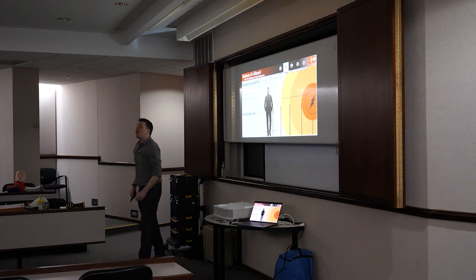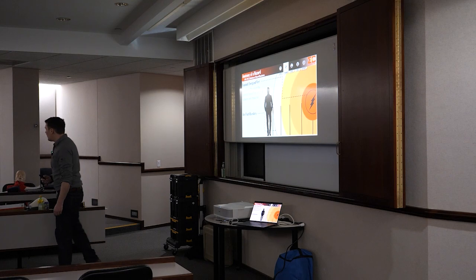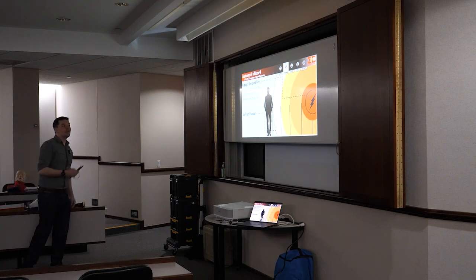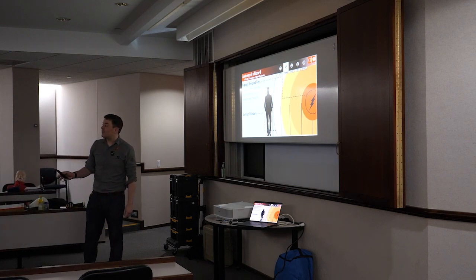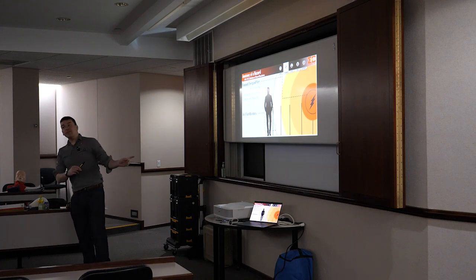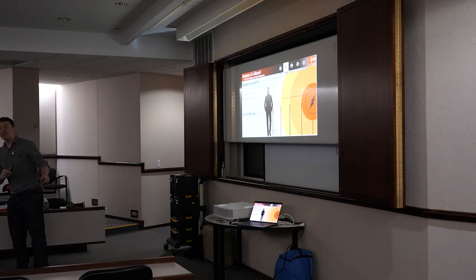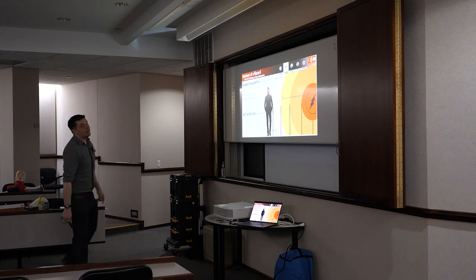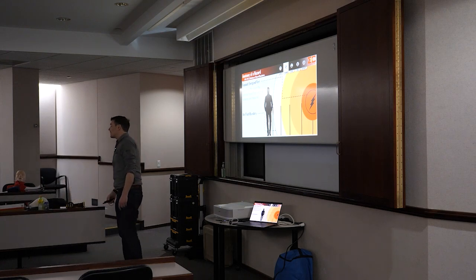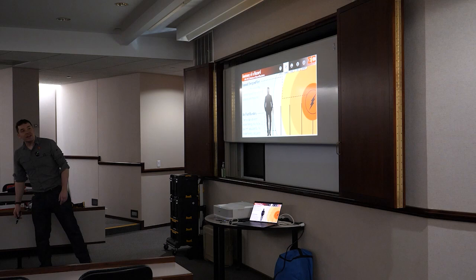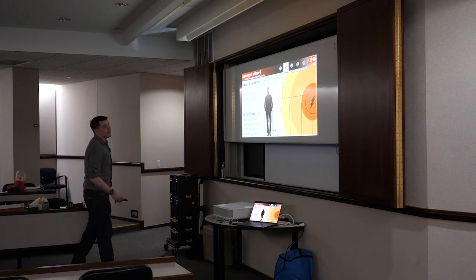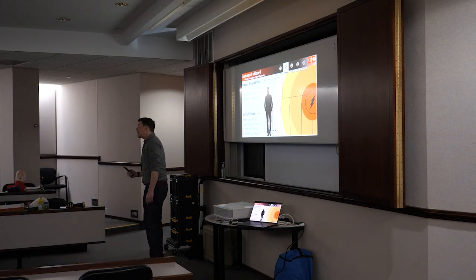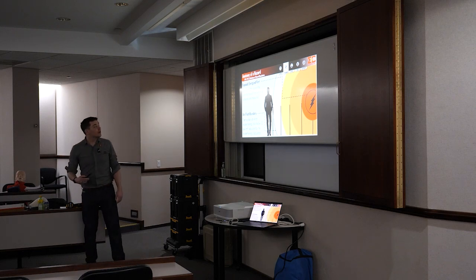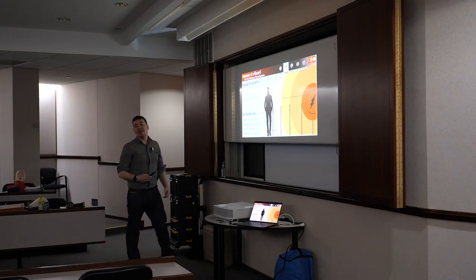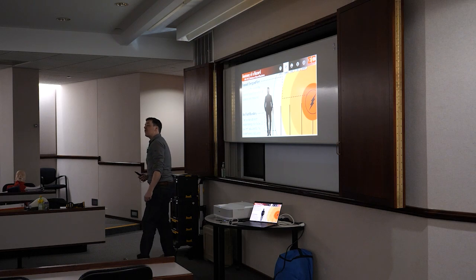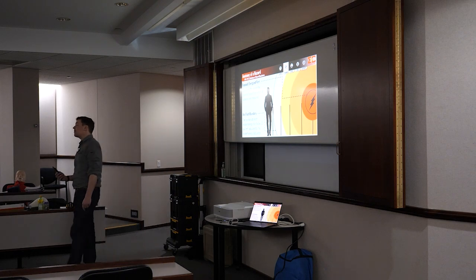Understanding what the different areas and what the different boundaries are when we deal with the equipment. For those of you who are looking to take your NETA exam, you should be very familiar with these because NETA 2 and NETA 3 love to throw questions about the shock protection and arc flash protection boundaries. At the center of it is going to be the exposed energized part. That is where the flash or incident is potentially initiated. Going out from there, there is going to be the arc flash boundary. That is the point at which your incident energy falls down to 1.2 calories per centimeter squared or less.